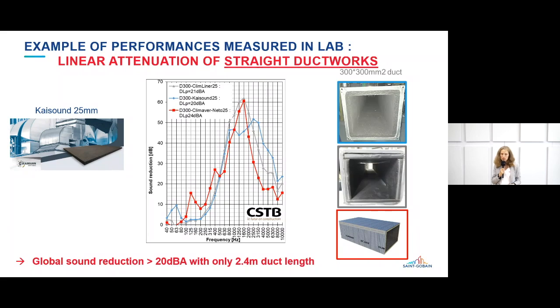Those are the curves. We didn't put the CLIMAVER because they were flat. They were like the bare metallic ducts. Here you can see the curves of two insulation materials that you put inside, which were the CLIMLiner and the Kaisound. They were both of 25 millimeters. And you have also the red curve, which is CLIMAVER A2 Neto. And what you can see is that for all three systems, you can have a linear attenuation over 20 dBA on only 2.4 meters. That is to say more than 7 dBA per meter. And this was on the 30 per 30 centimeter ducts.